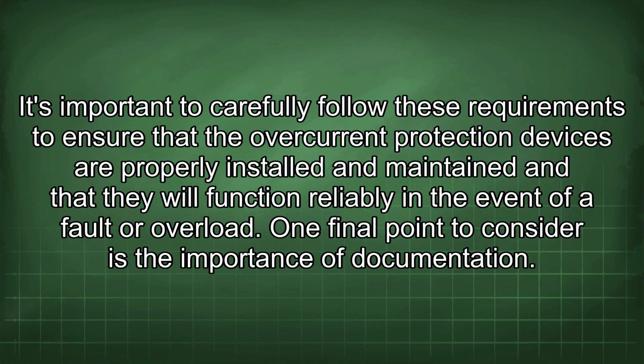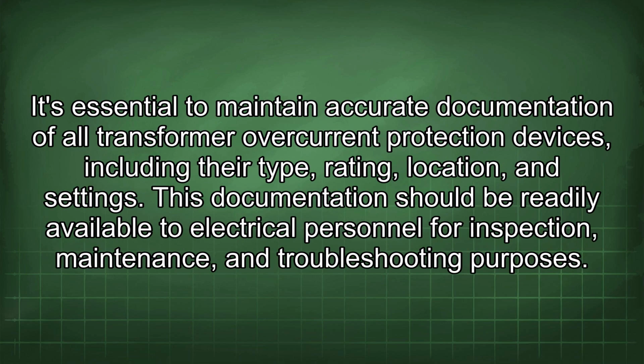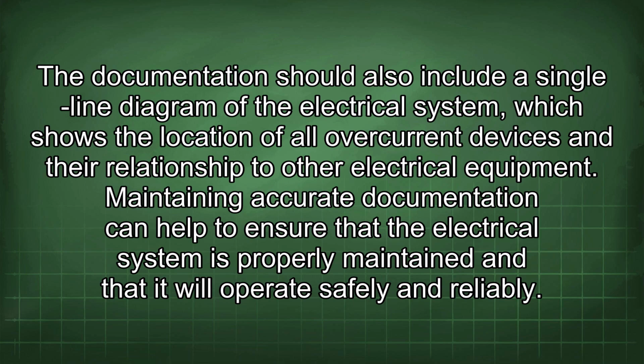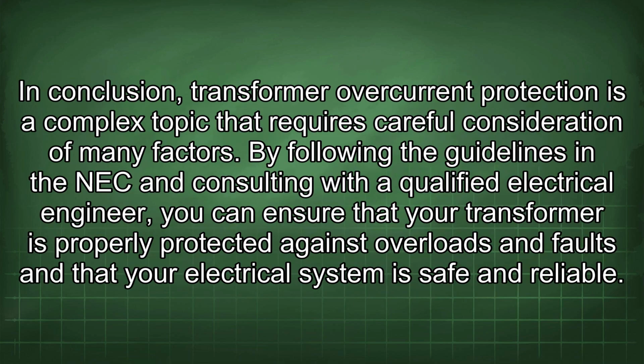One final point to consider is the importance of documentation. It's essential to maintain accurate documentation of all transformer overcurrent protection devices, including their type, rating, location, and settings. This documentation should be readily available to electrical personnel for inspection, maintenance, and troubleshooting purposes. The documentation should also include a single-line diagram of the electrical system, which shows the location of all overcurrent devices and their relationship to other electrical equipment. Maintaining accurate documentation can help to ensure that the electrical system is properly maintained and that it will operate safely and reliably.